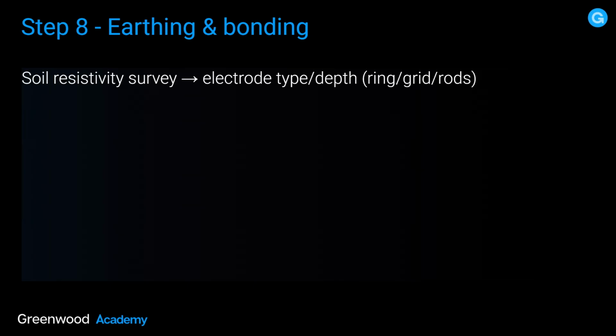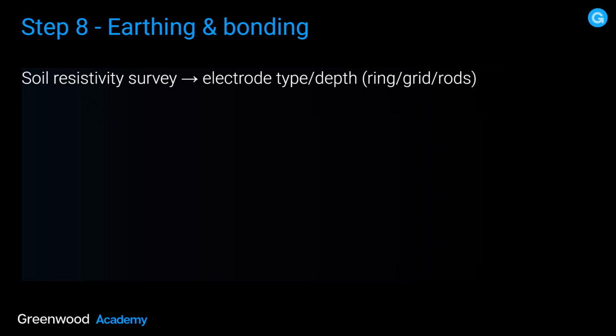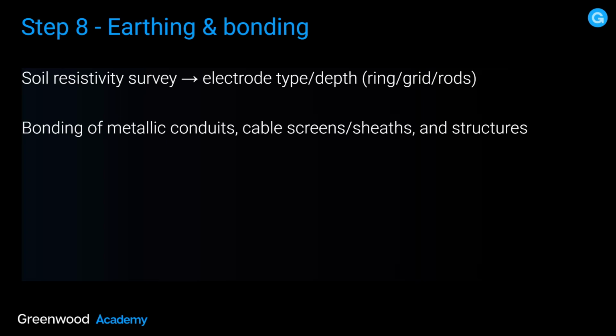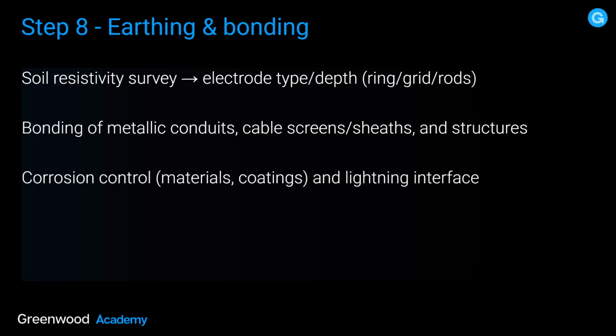Step 8, earthing and bonding. Now, remember, obviously, you have to take this into consideration as well. Earthing on solar farms is an art in itself for those who understand it. So spend the time to plan your earthing and bonding schedule carefully. So we're talking about a soil resistivity survey, electrode type, depth, whether it's ring, grid, rods, bonding of metallic conduits if used, cable screen, sheaths and structures, corrosion control, materials, coating, and lightning interface. Now, lightning protection is a course in itself, which we're not covering here, but we will be covering it in the future very soon, specifically for solar farms.